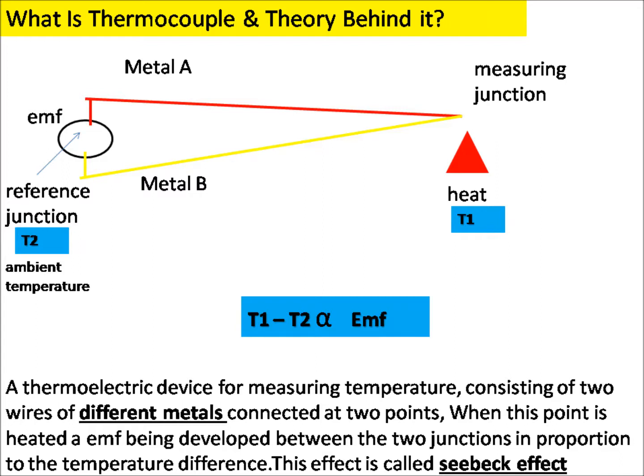In figure 1, metal A and metal B are dissimilar metals connected at a point called the measuring or hot junction. When this junction is heated, an EMF is induced which is directly proportional to the temperature difference between the two junctions. Remember: a thermocouple does not measure the exact process temperature — it measures the difference between the exact temperature minus the reference temperature, which is the ambient temperature. To get the exact process temperature, you must add the ambient temperature.